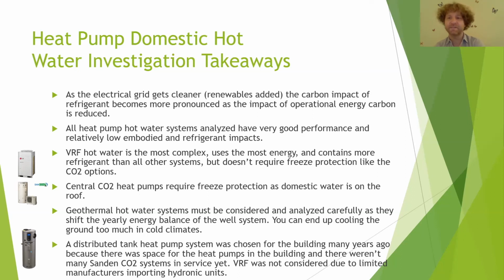I already mentioned that the VRF is a bit complex, but it doesn't have any freeze protection issues, because there's a VRF unit on the roof that will never freeze. Whereas all the carbon dioxide based heat pumps put actual water up onto the roof. Normally freeze protection isn't an issue, because when the units are on they manage that themselves, but if you lose power, you've got to be careful. So you have to provide ways of making sure those machines don't freeze up on the roof.